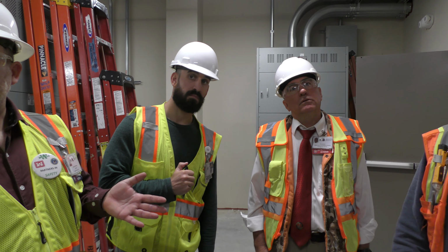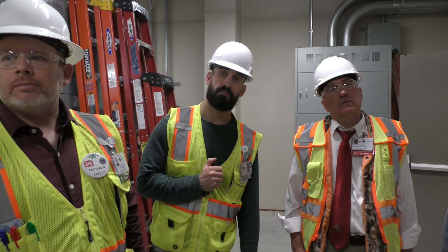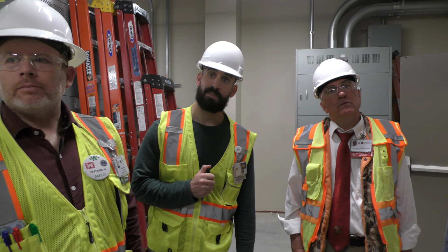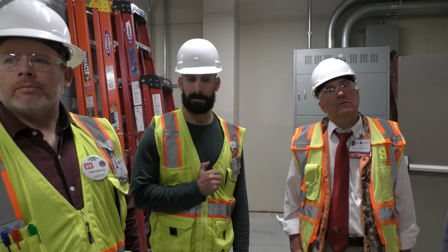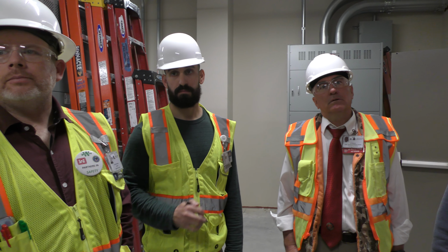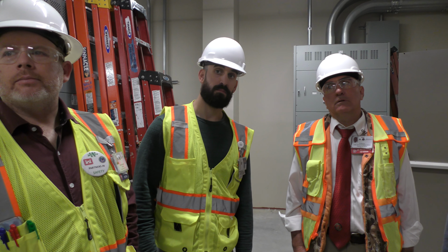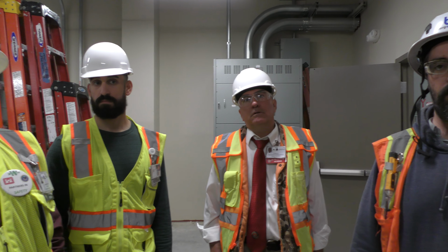I thought that was the mass notification. No, mass notification is actually a whole other unit that's integrated into the fire alarm control panel that produces mass notification throughout multiple campuses with the same message. So you guys don't have that, it's just locally within your campus. A lot of people say it's mass notification, but there's a whole other system that adapts to that.